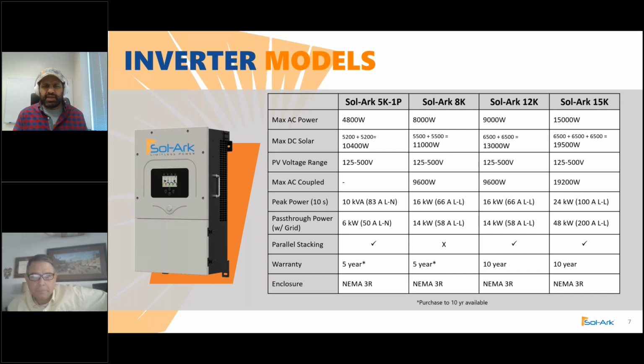The 5K 1P and the 8K, the 8K is basically a more powerful version of the 5K. The 1P, by the way, is an actual one phase or single phase inverter, so it can actually be stacked, but it'll either do 120 or 240. The 8K inverter is not stackable, but it's a split phase output, so you'll get two hot conductors and a neutral.